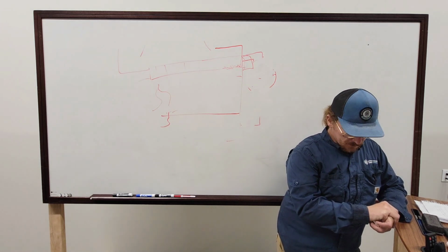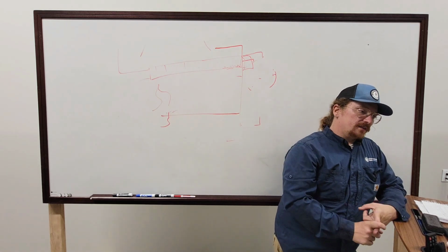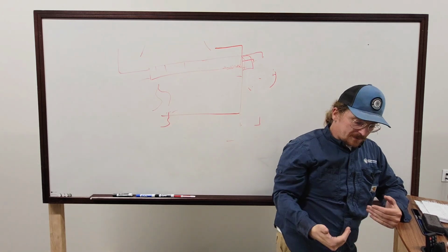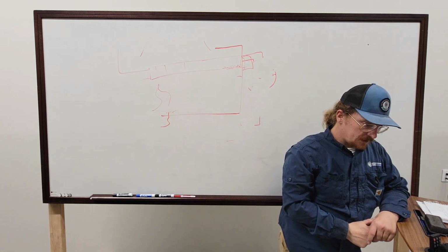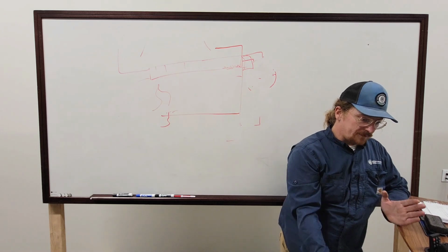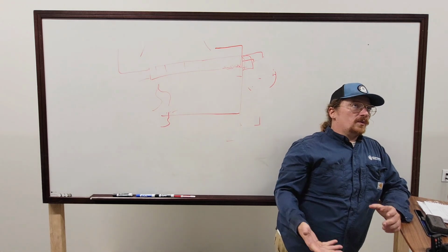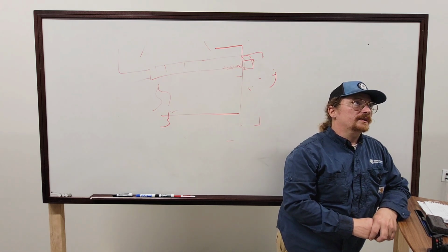Any maintenance will involve that. Tightening your electrical connections. Checking your flue, putting your phone up in there and making sure you have a flue. A lot of times it involves pulling the burner rack out, which is very involved. But that's where reading the manual comes in, because the manual may say that you may never need to service the burner rack. Well, then maybe just look at it. If it says once a year, scrub it with water, that's where that's going to come into play. If there's no manual, then it's better judgment.